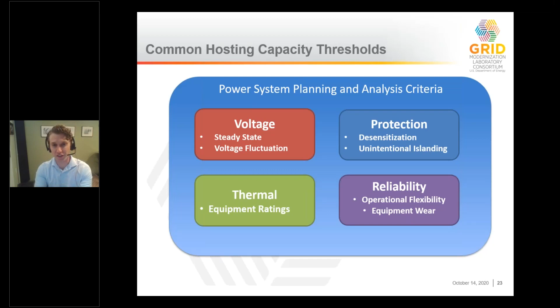This chart may look familiar if you saw my presentation from yesterday. Reverse power flow from DER can create high voltage, and there are set limits that equipment can tolerate. So an important evaluation during hosting capacity is what the steady state voltage will be after DER is added.